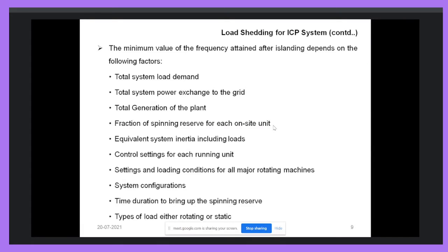Equivalent system inertia is a very much related parameter, because, as we studied in our undergraduate course also, the frequency deviation depends on the inertia of the generator, or you can say the equivalent inertia of the system, in which we consider load inertia also. Load inertia means the inertia of rotating loads. So the equivalent inertia will also affect the deviation of frequency. If the islanded plant has a larger value of inertia, then the frequency deviation will be low. There is an inverse relation between frequency deviation and the equivalent inertia of the system.